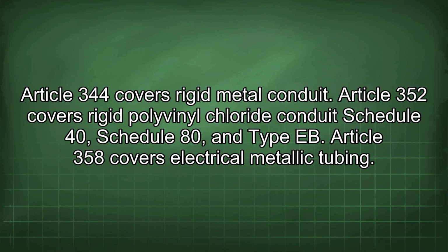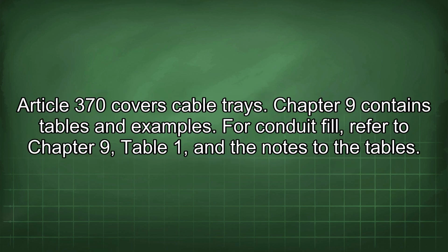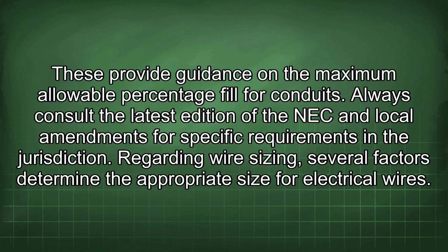Article 344 covers rigid metal conduit. Article 352 covers rigid polyvinyl chloride conduit Schedule 40, Schedule 80, and Type EB. Article 358 covers electrical metallic tubing. Article 370 covers cable trays. Chapter 9 contains tables and examples. For conduit fill, refer to Chapter 9, Table 1, and the notes to the tables. These provide guidance on the maximum allowable percentage fill for conduits. Always consult the latest edition of the NEC and local amendments for specific requirements in the jurisdiction.